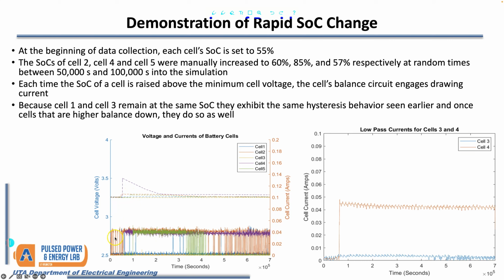You'll see right here a little hysteresis every once in a while, where it thinks the orange cell is slightly above and turns on that balance. We think this is a consequence of the dynamic balancing threshold, which might continuously dissipate a cell or two if it measures the voltage incorrectly, resulting in a BMS that balances a cell even when it's actually pretty close to balance.